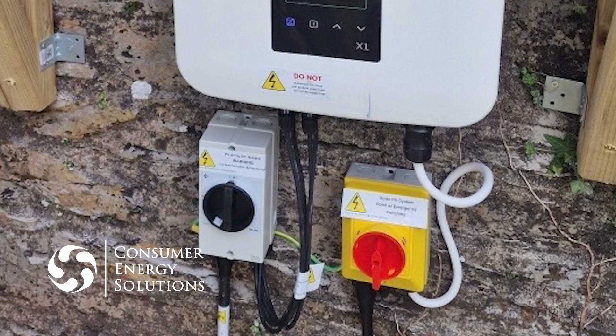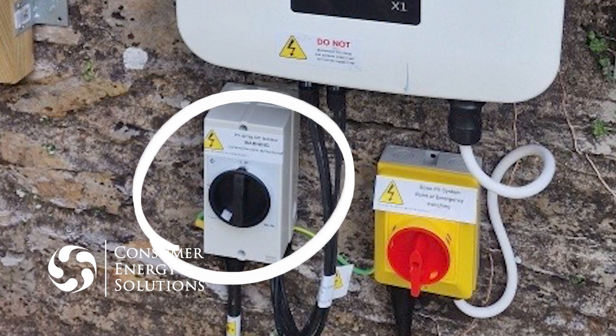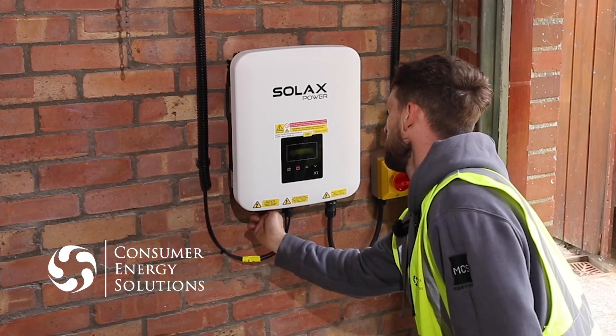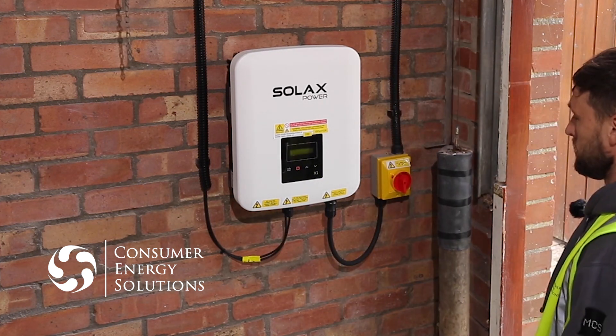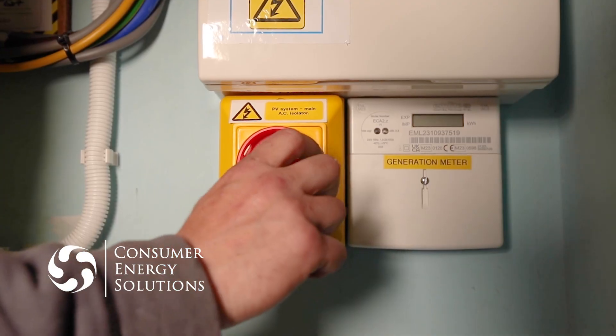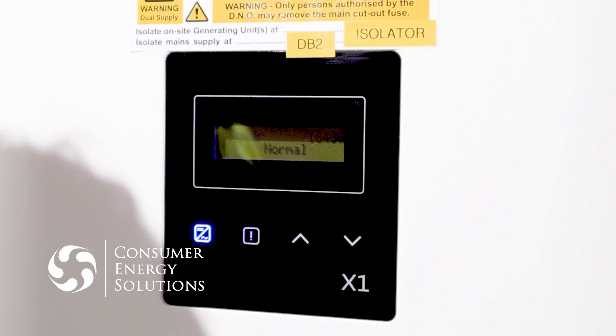In some installations, a second isolator is installed near the inverter. Wait five minutes for the system to completely shut down. To turn the system back on, turn the DC isolator back on first, then the AC isolator next to the inverter, and then the AC isolator next to the consumer unit. Wait approximately one minute for the system to fire back up, and all error codes should have cleared.